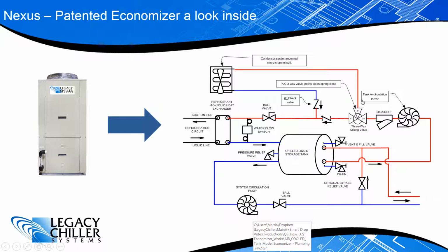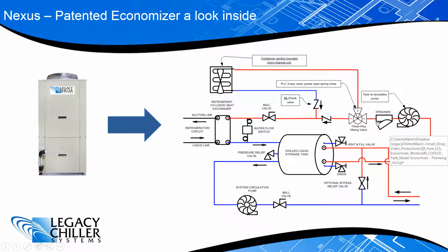And then we have our tank recirculation system, and this is actually integral to the economizer process. So the recirc pump draws off the tank, goes through the strainer. In mechanical mode, the connection is made between A and C in this mixing valve here. So in mechanical cooling mode, it's going from A to C through a check valve. Can't go this way because it's another check valve. This is a balancing valve for the pump through the chiller's evaporator, the refrigerant to liquid heat exchanger that's connected to the refrigeration system, and then back to the tank.